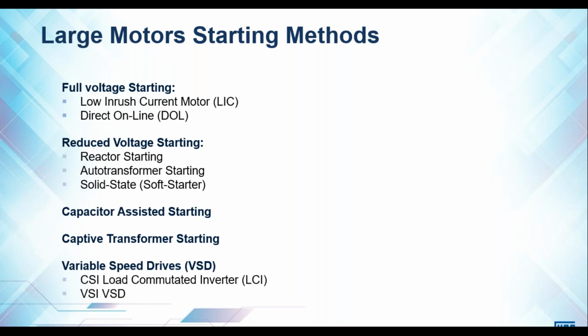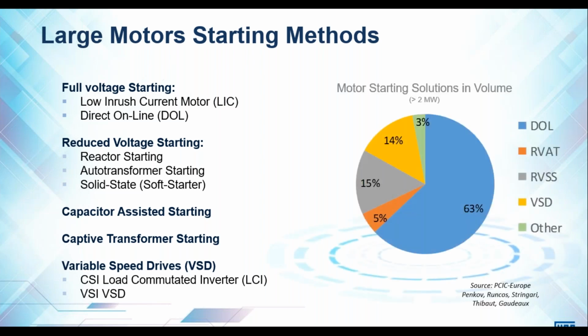All right, so these are also common knowledge. We're just summarizing some of the starting methods for large machines. So full voltage starting is either a low inrush current design motor, which we've discussed, or starting a standard squirrel cage machine direct online. Reduced voltage starting is making use of an indirect starter added to the circuit. In this case, the examples are reactor, auto transformer, or solid state soft starter. Capacitor assisted starting and captive transformer starting are not so common, and then there are variable speed drives as starting methods and speed control.